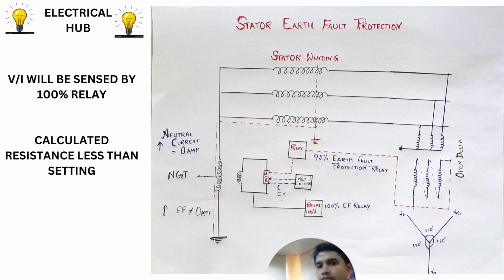In general, I is always 0, so V by I will be infinity. But when there is some current, V by I will be some resistance. The calculated resistance will always be lesser than the setting resistance. As soon as it senses the resistance, it will trip the breaker.